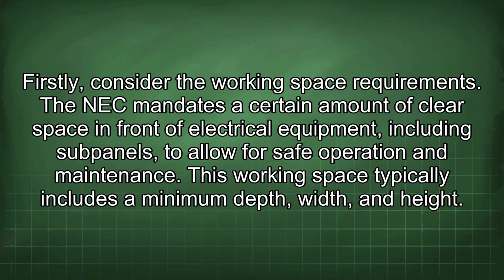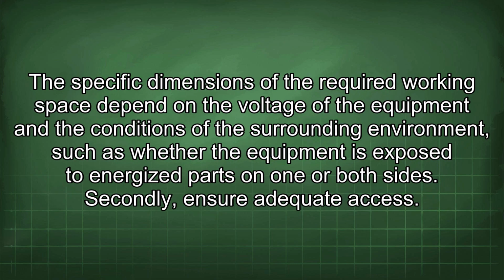Firstly, consider the working space requirements. The NEC mandates a certain amount of clear space in front of electrical equipment, including subpanels, to allow for safe operation and maintenance. This working space typically includes a minimum depth, width, and height. The specific dimensions of the required working space depend on the voltage of the equipment and the conditions of the surrounding environment, such as whether the equipment is exposed to energized parts on one or both sides.